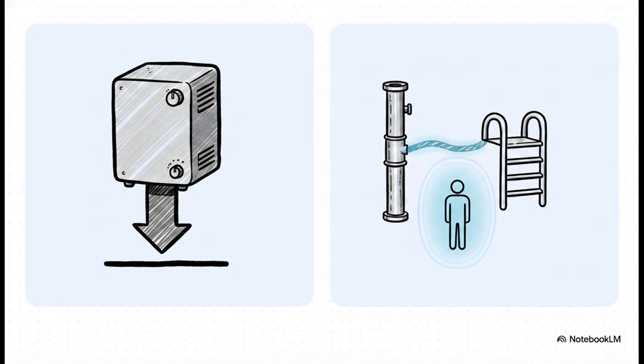So, while we've been talking a lot about routing fault currents to trip a breaker, high-risk wet areas present an entirely different kind of hazard. We're talking about dangerous voltage differences. It is absolutely vital that we clearly distinguish between these two concepts. Earthing, as we said, is about creating that low-resistance highway to the ground to clear a fault. Equipotential bonding, on the other hand, that's about physically connecting various exposed conductive parts together.